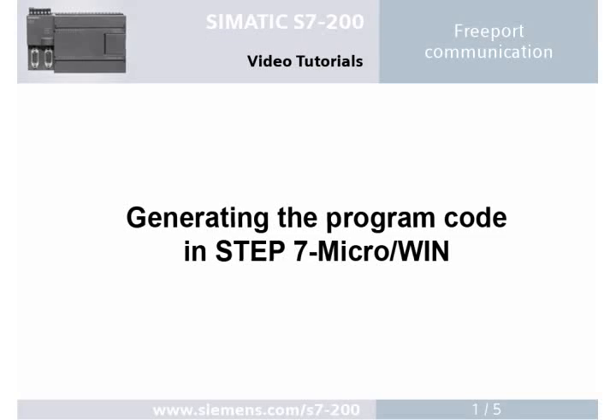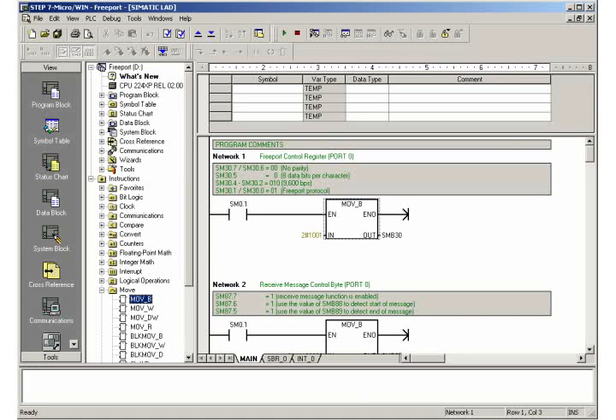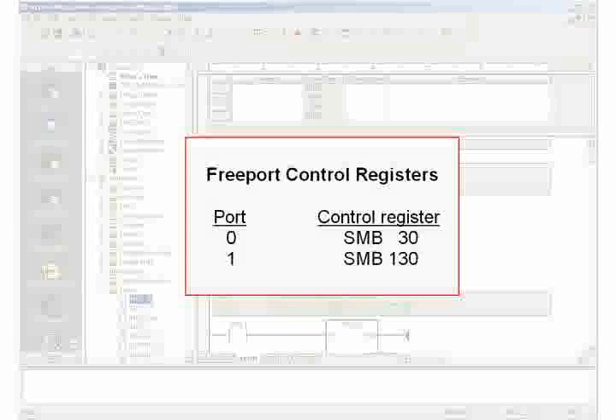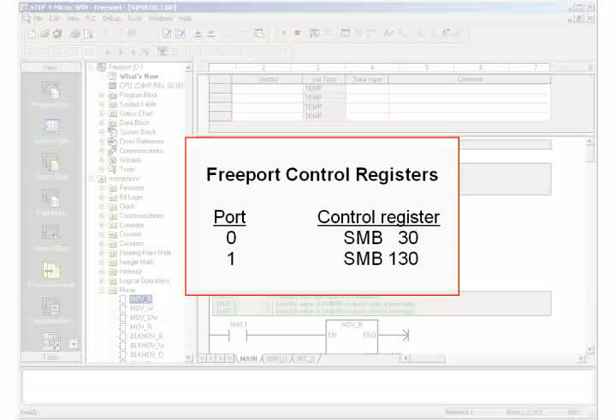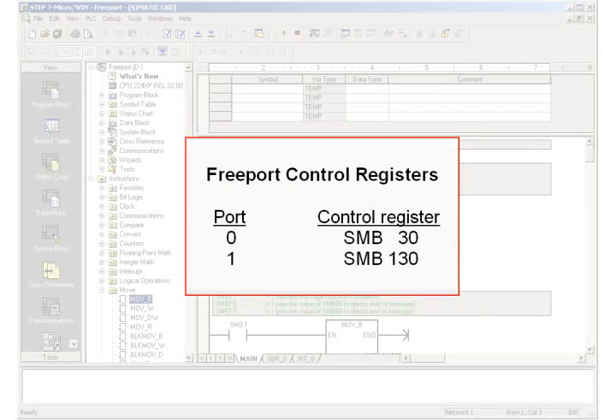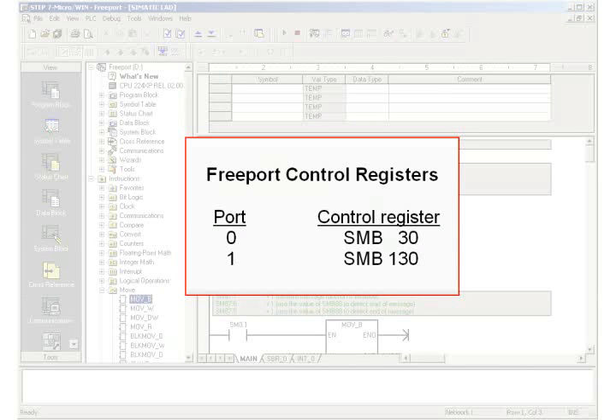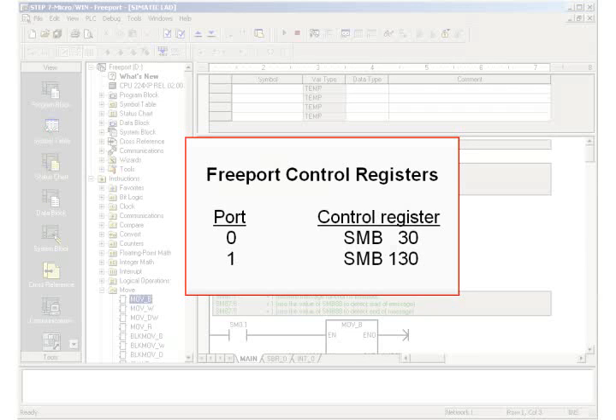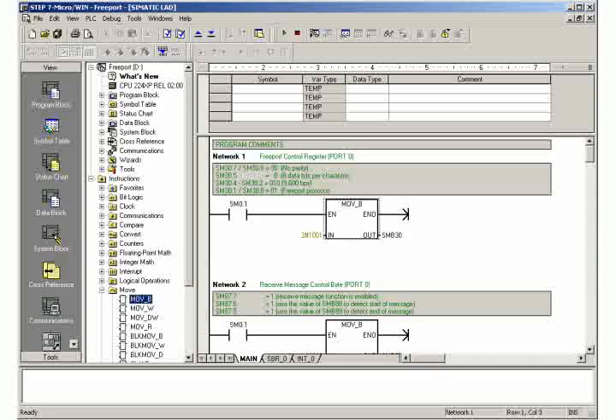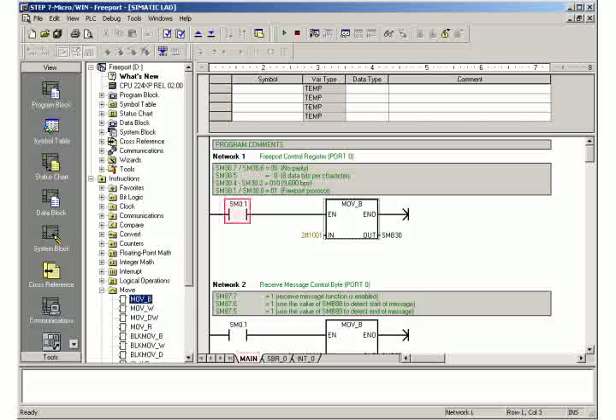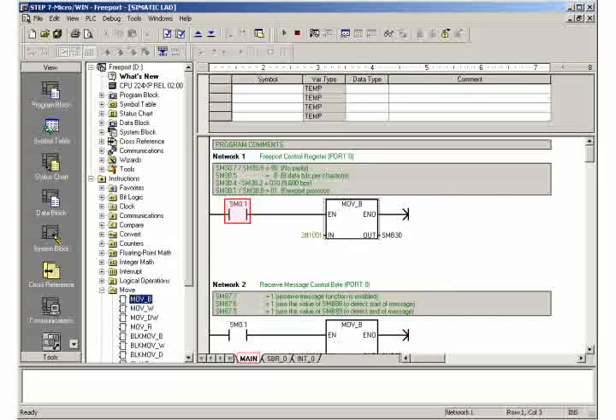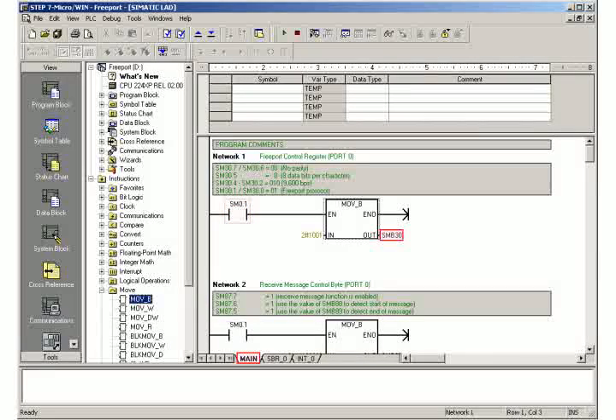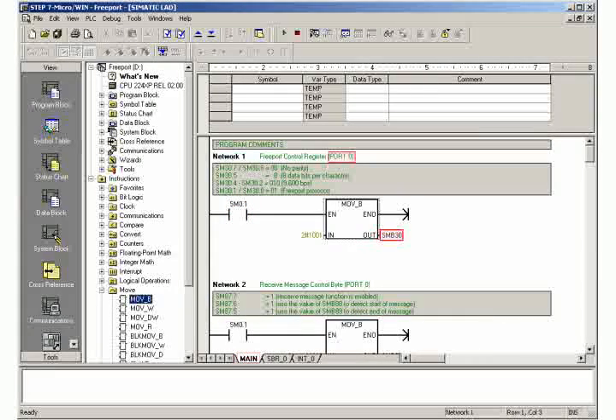Step 1: Generating the program code in Step 7 MICROWIN. For the free port communication, the control register SMB30 or 130 must be initialized depending on the used communication port. In network 1 of the operation block, you initialize the control register SMB30 for port 0.